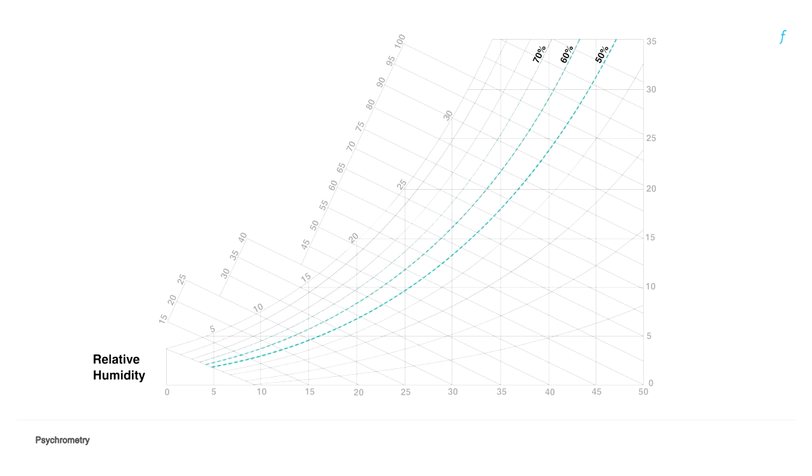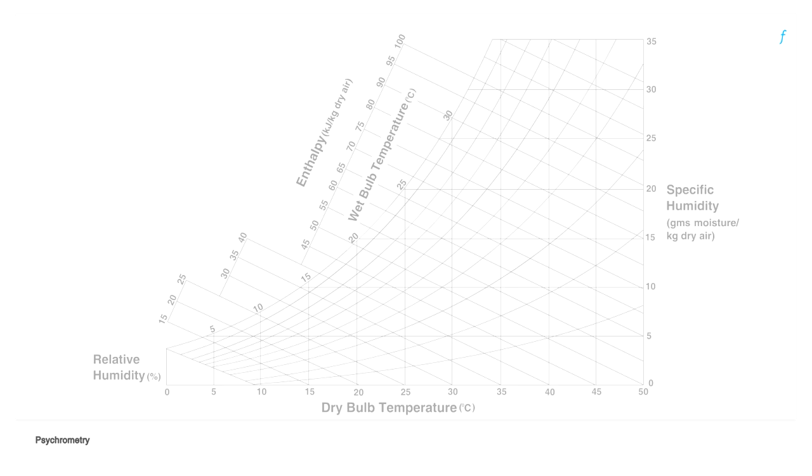So moving towards the right or left on the chart parallel to the x-axis would be sensible heating or sensible cooling where the dry bulb temperature changes without a change in the moisture content of air. Moving parallel to the y-axis would cause humidification or dehumidification, that is changes in humidity levels of air without changing the dry bulb temperature of air.